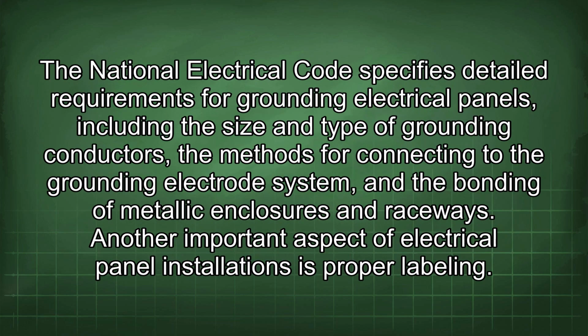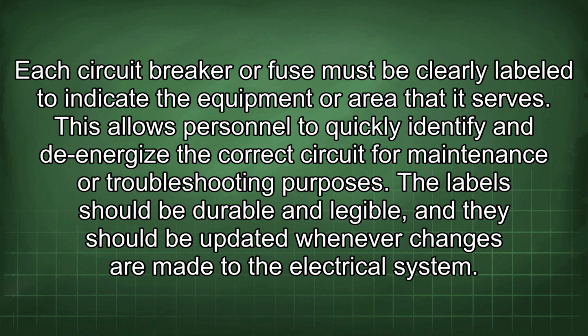The National Electrical Code specifies detailed requirements for grounding electrical panels, including the size and type of grounding conductors, the methods for connecting to the grounding electrode system, and the bonding of metallic enclosures and raceways. Another important aspect of electrical panel installations is proper labeling. Each circuit breaker or fuse must be clearly labeled to indicate the equipment or area that it serves. This allows personnel to quickly identify and de-energize the correct circuit for maintenance or troubleshooting purposes. The labels should be durable and legible, and they should be updated whenever changes are made to the electrical system.